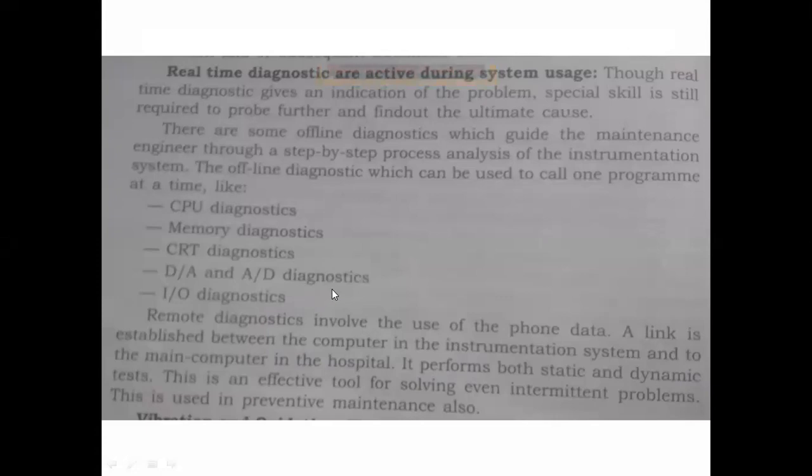We can diagnose the system statically and dynamically. It means that while the patient is being monitored, we can diagnose the system, and also without connecting the signals to the patient, we can analyze the diagnosis of the particular system. So it performs both static and dynamic tests. Dynamic tests means while measuring the signals from the patient.